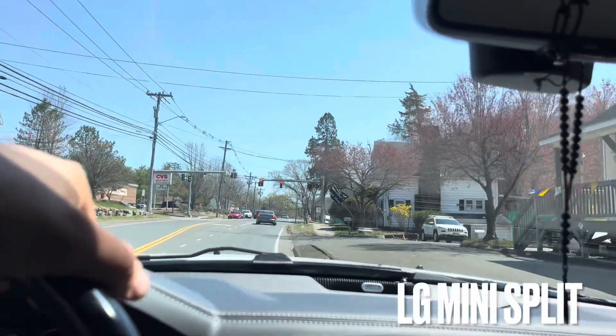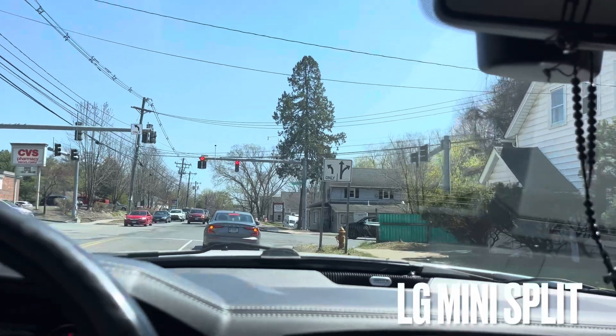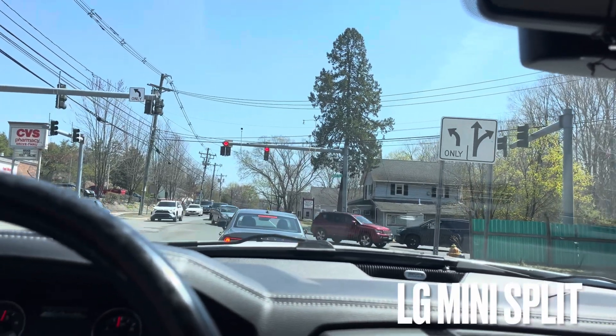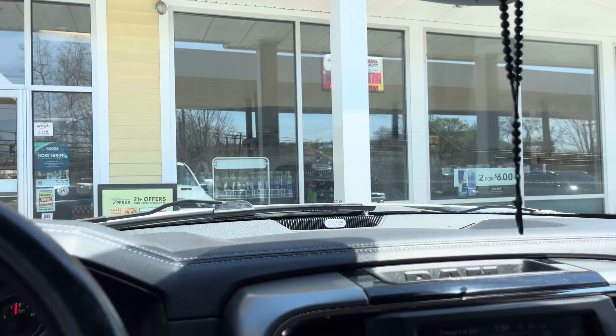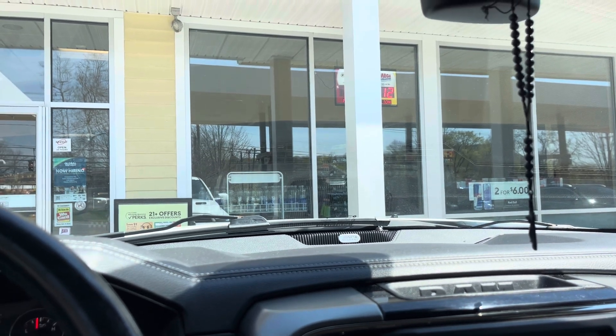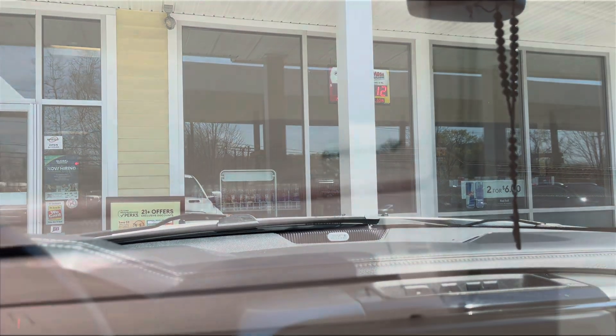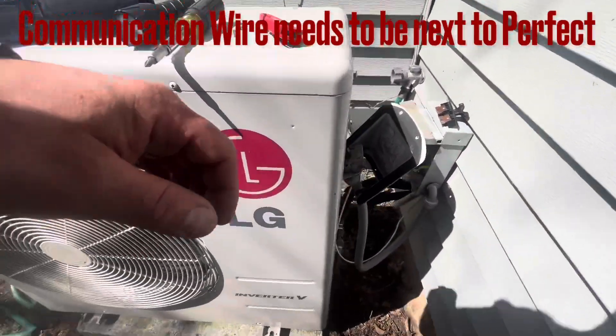She asked if I could go up there because she has five blinking lights on the unit — they're white lights, just five blinks. So there's an LG or Daikin with five white blinks inside as an error code, and we'll go see what it is.